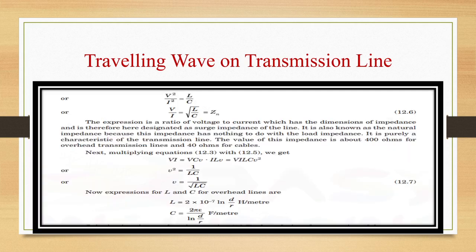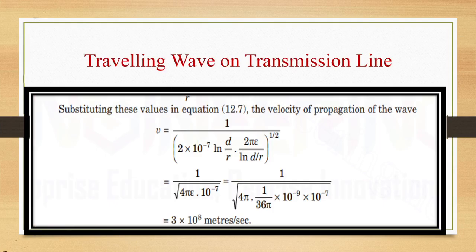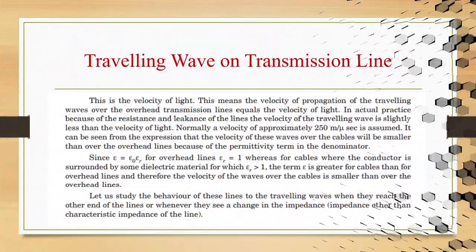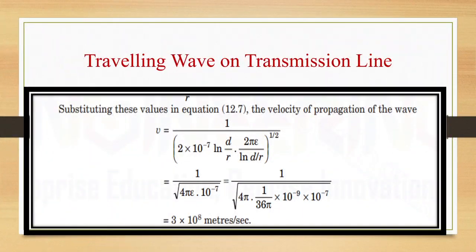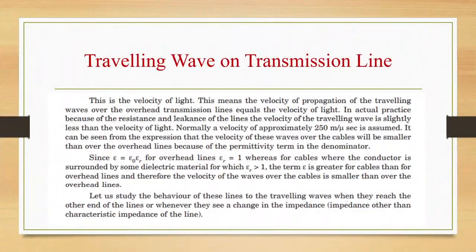We have derived the equations for current and voltage and obtained the velocity as 3×10⁸ meters per second after substitution of all values. This is the velocity of propagation of a traveling wave over an overhead transmission line. In actual practice, because of resistance and leakage of the lines, the velocity is slightly less than the speed of light. Normally a velocity of approximately 250 meters per microsecond is assumed. The velocity of waves in cables is smaller than in overhead lines because of the permittivity term in the denominator.